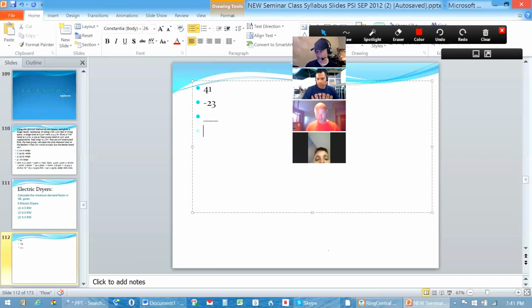So 41 minus 23 is 18 additional dryers. Each one of those dryers, like the previous example, but in this case only being 0.5%, I would take 18 dryers at 0.5% for each one of those. It would end up ultimately giving me 9% as a derate or a reduction on that derate factor.